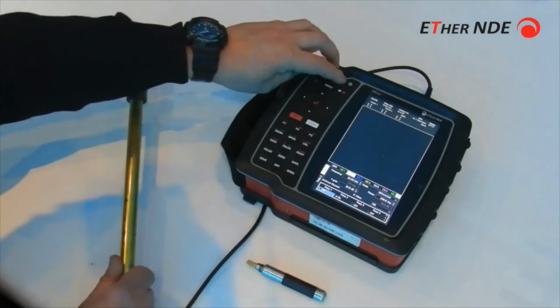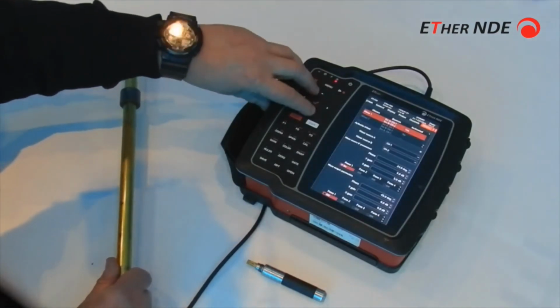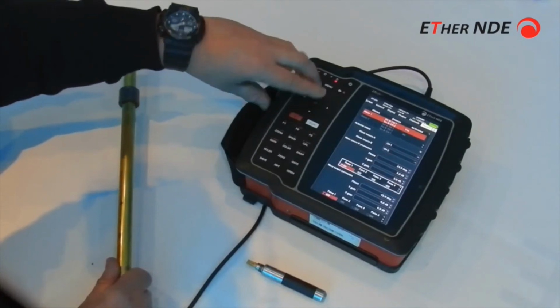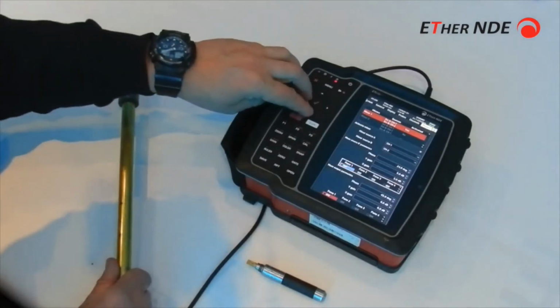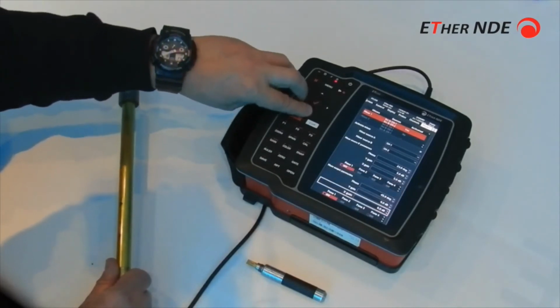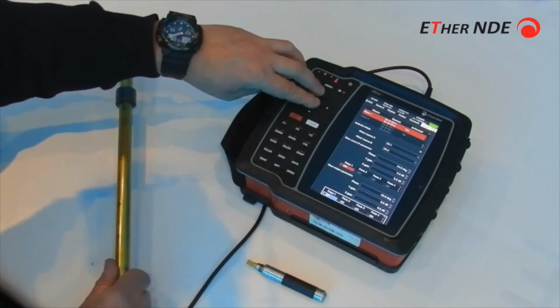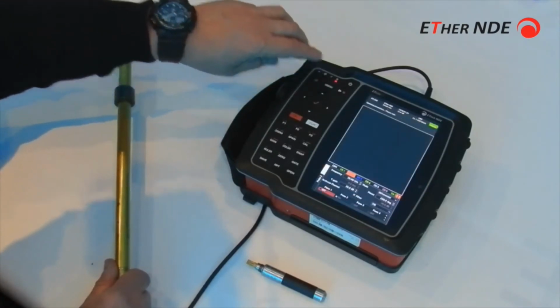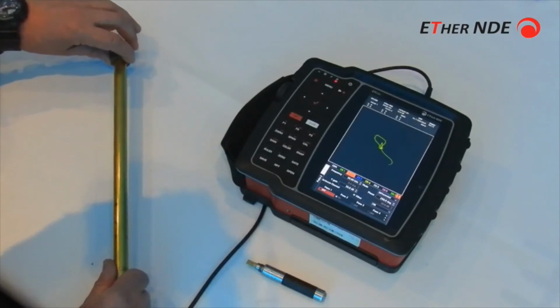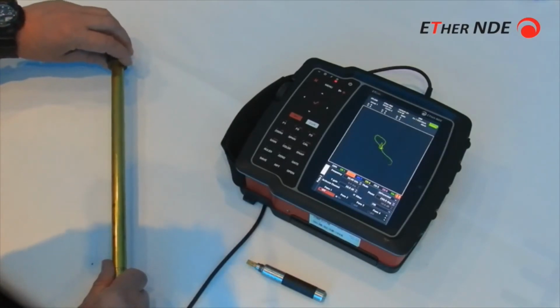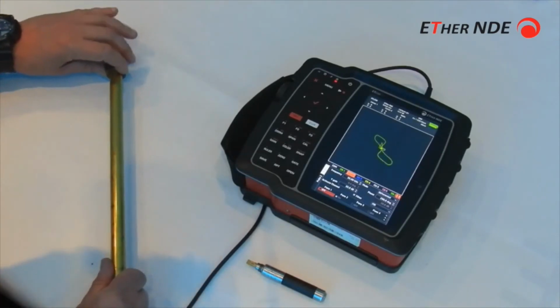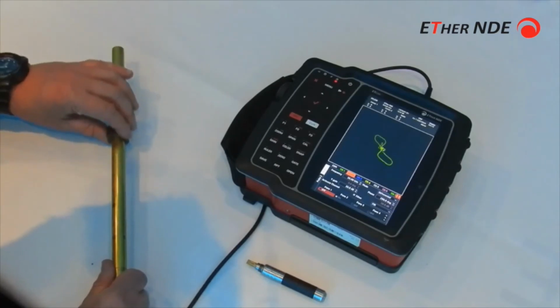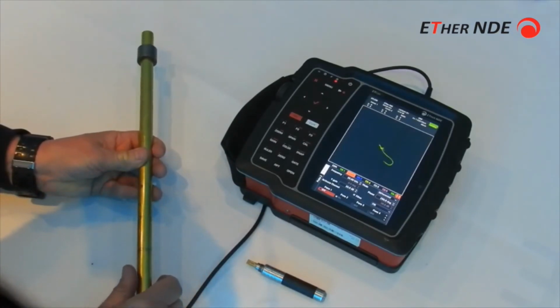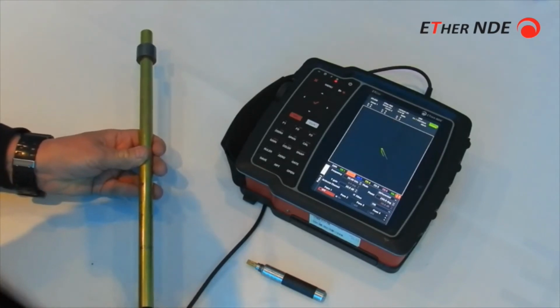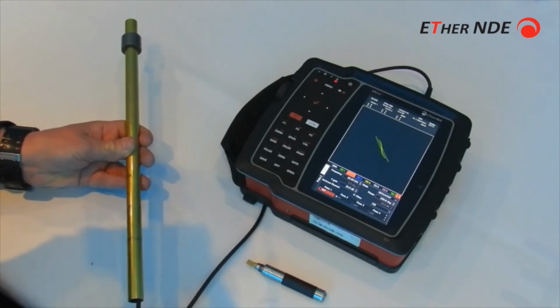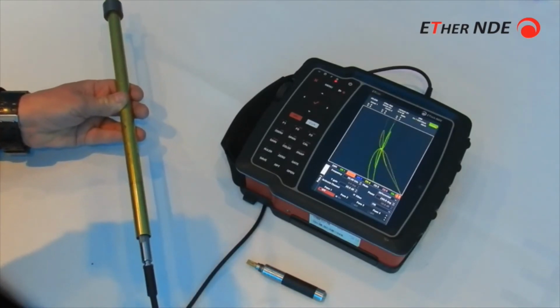The quick way of showing that is, now if I go down, switch off the display of the mix before subtraction, go down to the bottom, and now switch on the mix channel. What I've now got is the yellow signal is the residual signal from the mix, and the green signal is the original 20 kilohertz signal. So how does that now look versus the holes? If I now go along here, so that's residual, this is a drilled hole, so see the drilled hole still coming up. In fact, the signal's slightly larger. We're getting phase shift as before.